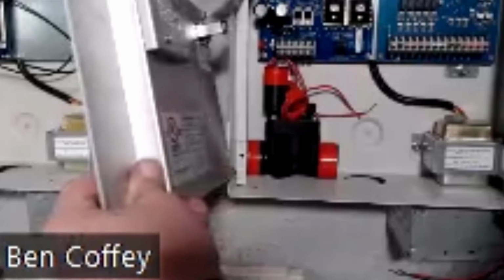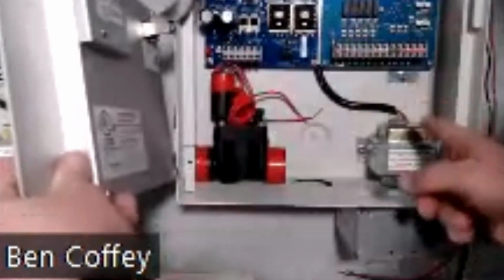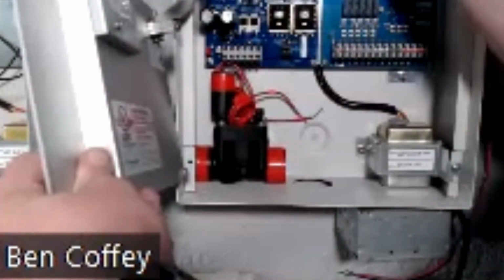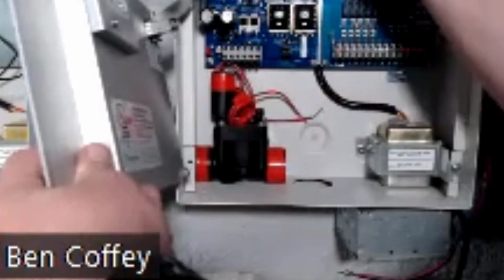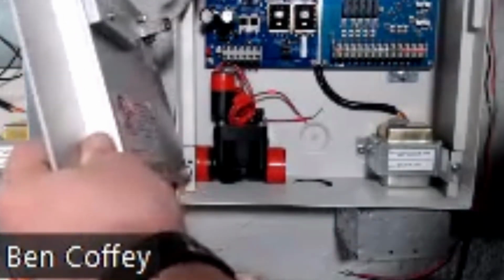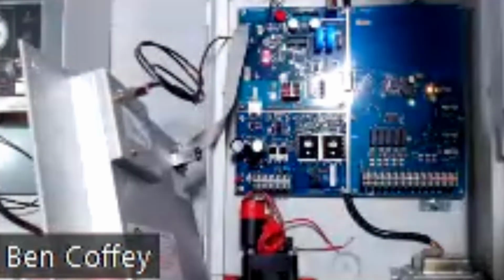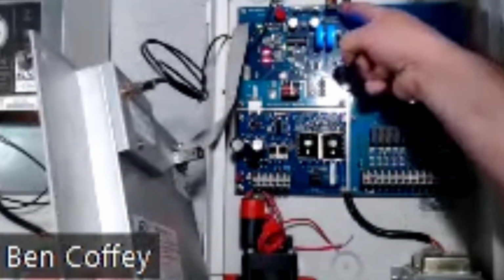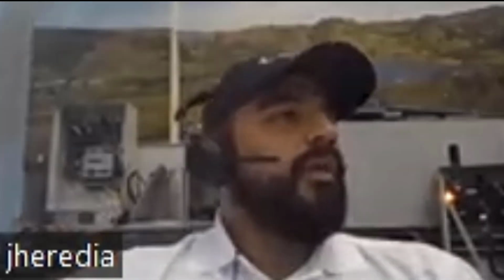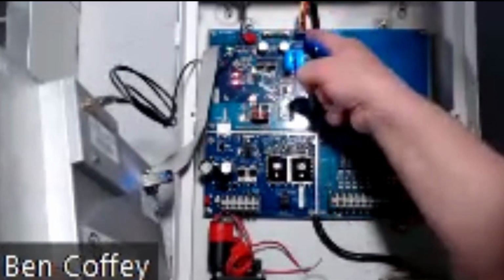Jonathan, take me through it. Down here at the transformer - both Pro 3 and the XR H2O use the same type of transformer, same configuration, same power options, standard from factory, and it works exactly the same way. If you zoom in a little on the first circuit board on the upper left where our transformer is connected, you'll notice this is actually a similar design to our Pro 3. The transformer then feeds our 24 volts to our mini chassis, and we have the 24-volt light on our bigger board.